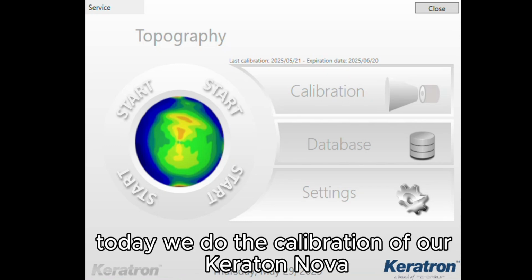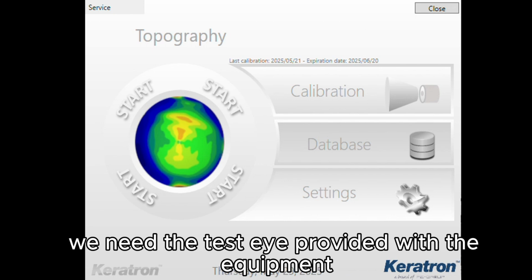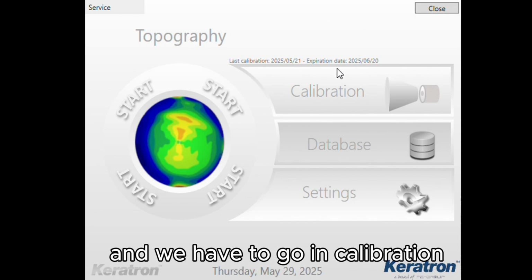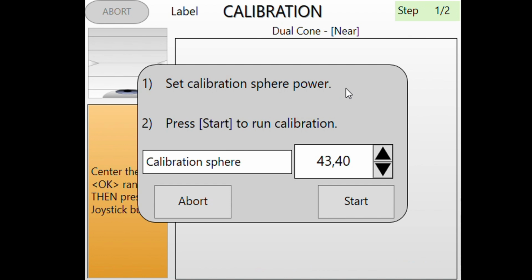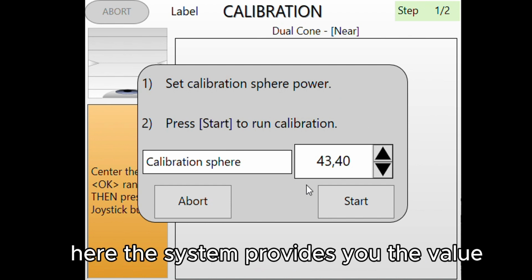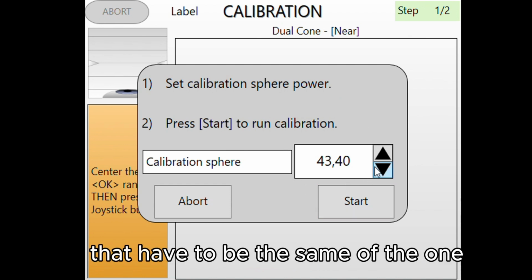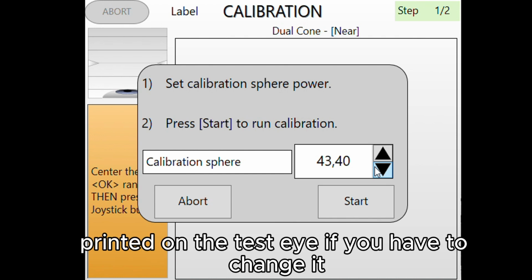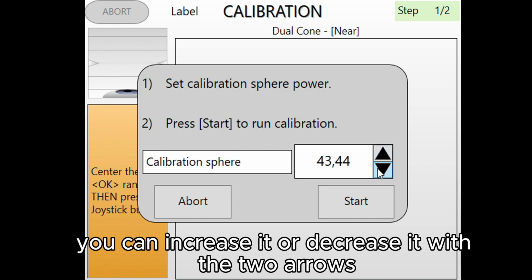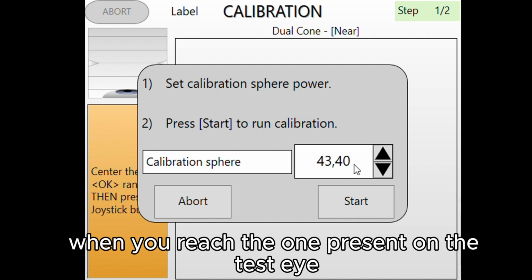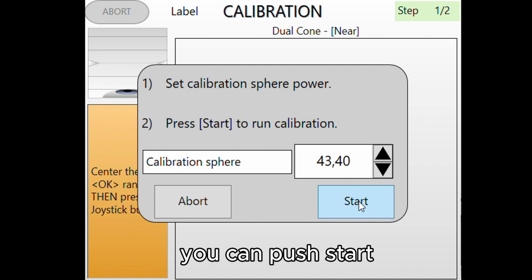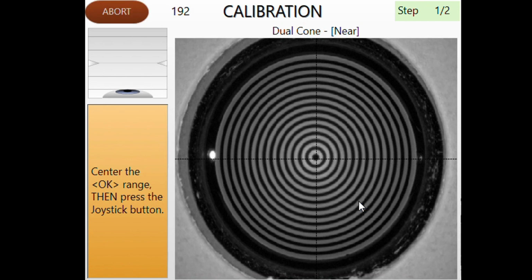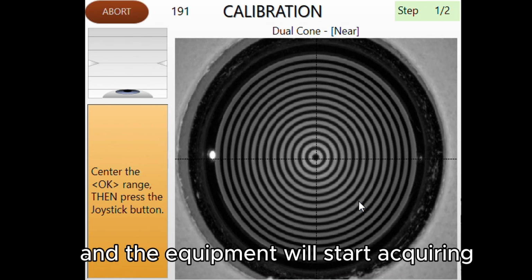Hi to all. Today we do the calibration of our Keratron NOVA. To do that, we need the test eye provided with the equipment, and we have to go in calibration. Here, the system provides you the value that has to be the same as the one printed on the test eye. If you have to change it, you can increase it or decrease it with the two arrows. When you reach the one present on the test eye, you can push start, and the equipment will start acquiring.